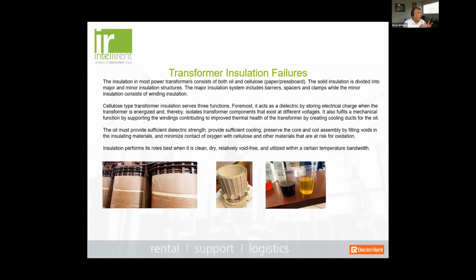Okay, the oil has to provide sufficient dielectric strength, and that provides sufficient cooling. It'll preserve the core and coil assembly by filling voids in the insulating materials and minimize contact of oxygen with the cellulose and other materials that might be at risk of oxidation. You can see here, it's similar to what you have in your automobile. Okay, the lubricating properties of oil start to degrade over time, and it becomes dingy and dark and full of sludge, while it should look like this nice clear sample over here.